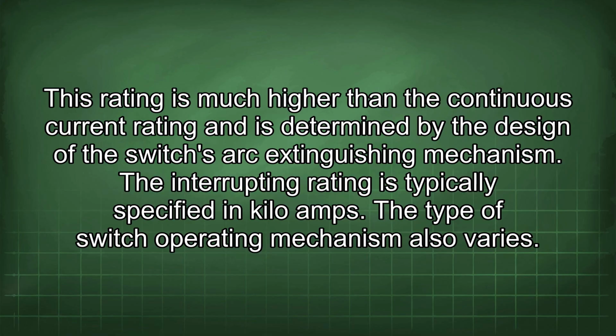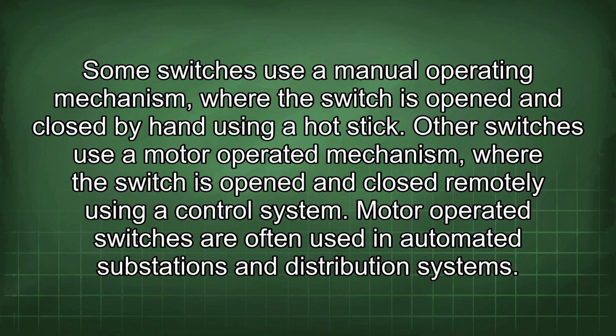The type of switch operating mechanism also varies. Some switches use a manual operating mechanism, where the switch is opened and closed by hand using a hot stick. Other switches use a motor-operated mechanism, where the switch is opened and closed remotely using a control system. Motor-operated switches are often used in automated substations and distribution systems.